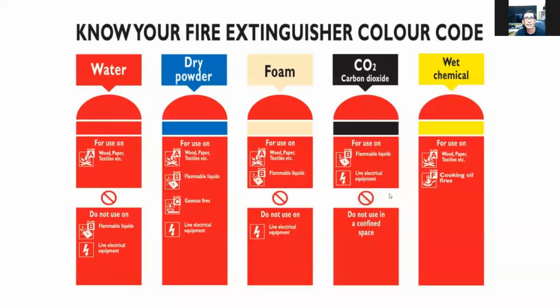So know your fire extinguisher based on color code. If there is a red line on top of the fire extinguisher, it means that the material inside is water. If there is blue, the material inside is dry powder. If there is beige, it is foam. If there is black, it is carbon dioxide. If it is yellow, it is wet chemical. So every type of material inside the fire extinguisher has a different use.